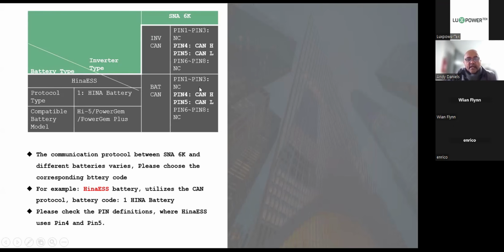And then on the battery side, we're just referring here to the HANA battery. Pin 4 is also CAN high, pin 5 is CAN low, so it takes a straight through cable. It works great. Right, so our example here uses the HANA battery, and it's got the compatible battery models, obviously the Hi-5, the PowerGem, and the PowerGem Plus. The PowerGem Plus is our new model that we introduced this year. It's a 14.3 kilowatt-hour battery. A nice chunky 280 amp hour high G prismatic cell in there with a 0.5 C discharge, which gives you about 7.2 kilowatts max continuous.